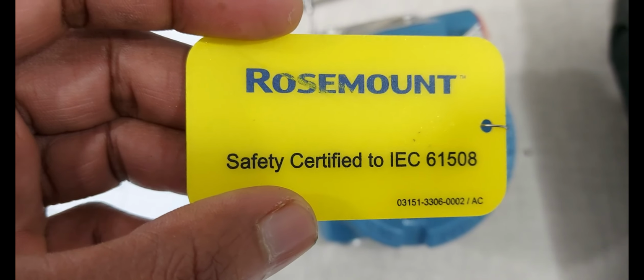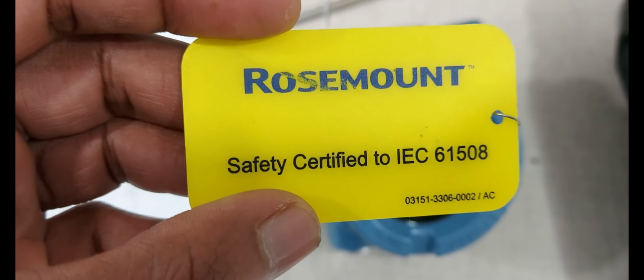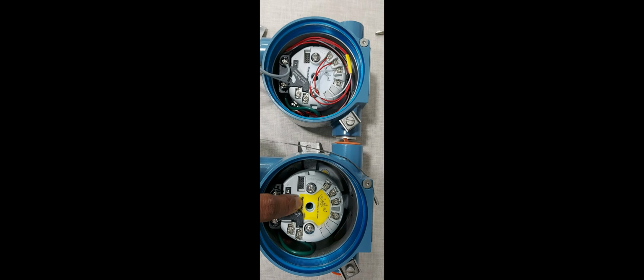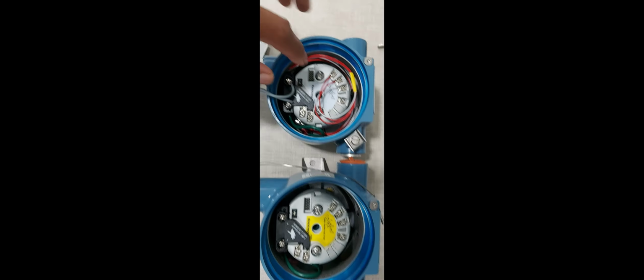Normally this transmitter is used for the ESD system. This is a normal type temperature transmitter. This is a SIL type temperature transmitter. The color code is already mentioned: yellow color is the SIL type, white color shows the normal transmitter.